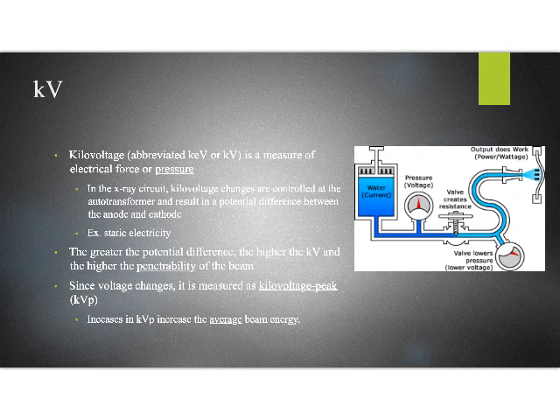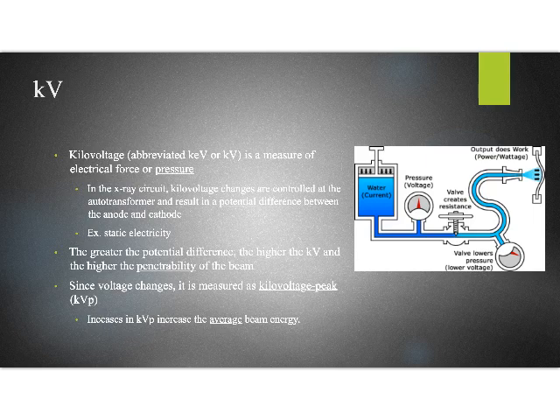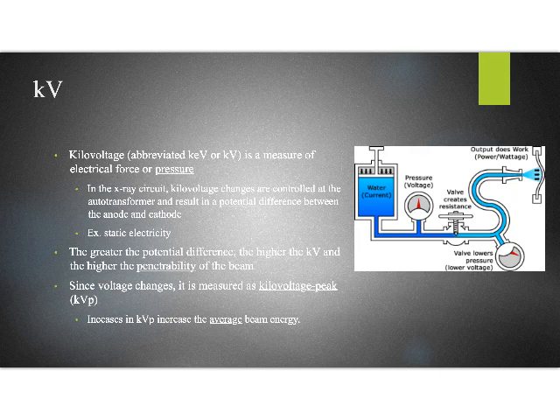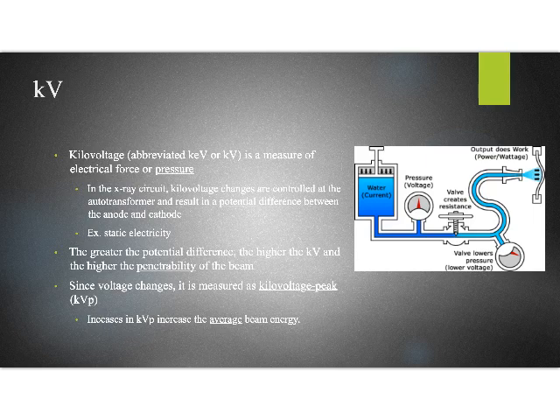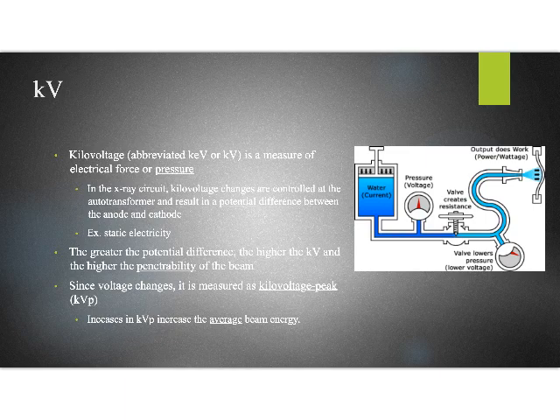Sometimes kilovoltage will be abbreviated KEV, kiloelectron volts, or KV, kilovoltage. When we're talking about it as a technique, we're talking about a kilovoltage peak. What is the peak energy? And then there's a number of average energies that would fall beneath that peak. So increasing the KVP increases the average beam energy. It increases the average penetrability of the x-ray beam. That's discussed pretty much pages 249 through 251 in our textbook.